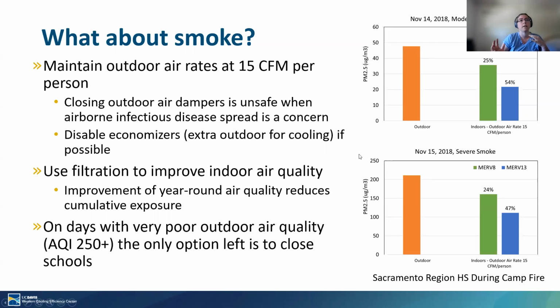I started to get concerned when, as far as I am aware, there is no engineering solution that can make a classroom safe from an air quality perspective on a really severe smoke day. When your outdoors starts to reach that hazardous level like 250 micrograms per meter cubed, your capacity can only filter so much, and if you're still trying to ventilate, you're just in a rock and a hard place. And so I think there needs to be some recognition that there are maybe some days where schools can just not operate, and that as of right now we don't have engineering solutions to make that possible. I think those days are really limited, but having some acceptance of that would help in planning.